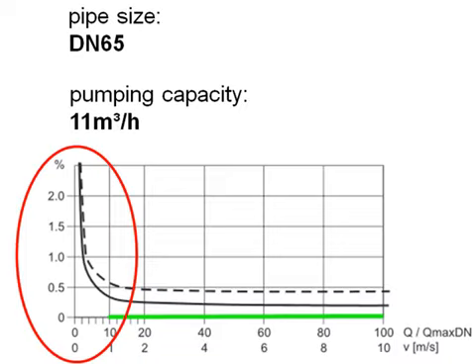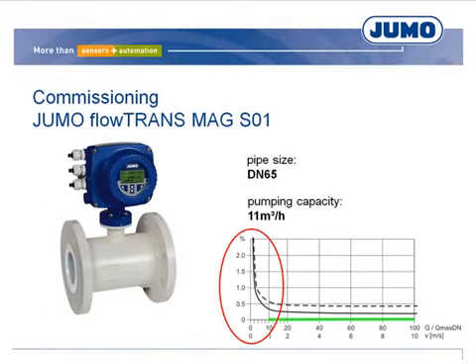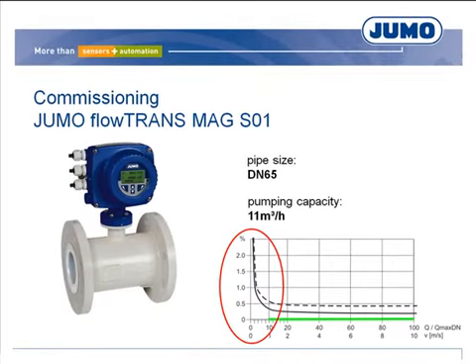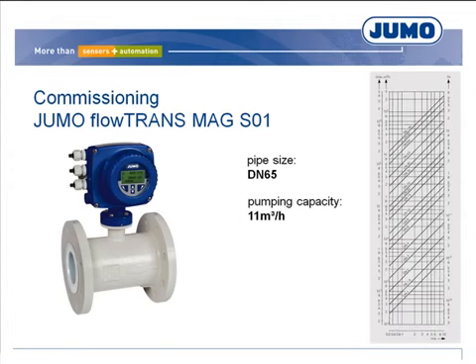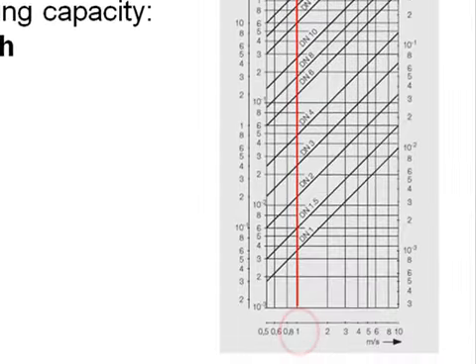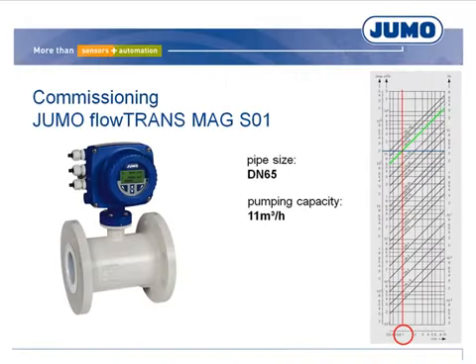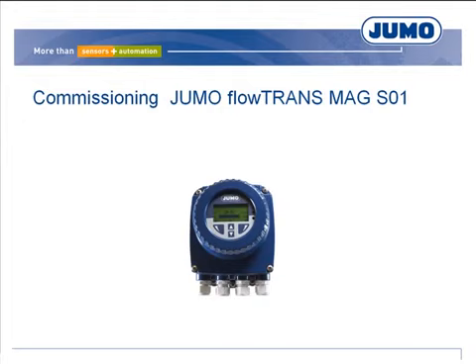Since the measurement error is higher in the lower measuring range, a reduction in front of the MID can be installed to increase the flow rate locally. To check if the flow velocity lies within the measuring range, so-called nomographs are used, as they can be found in the datasheets. With a specification of DN65 and a pumping capacity of 11 cubic meters per hour, a flow velocity of circa 1 meters per second results. The review was positive. The MID can now be ordered in DN65.